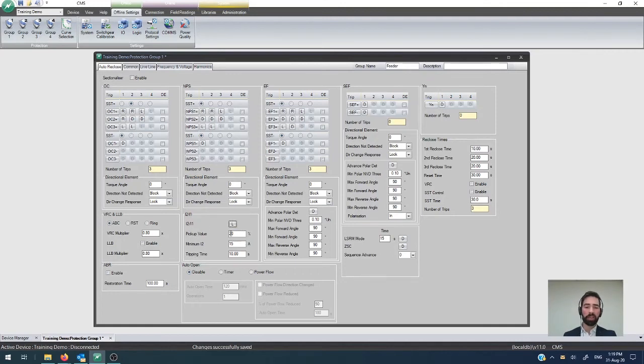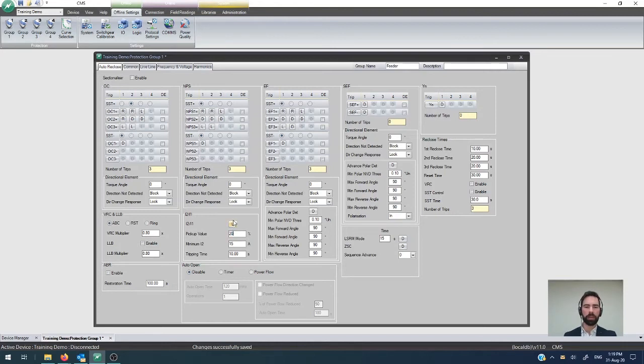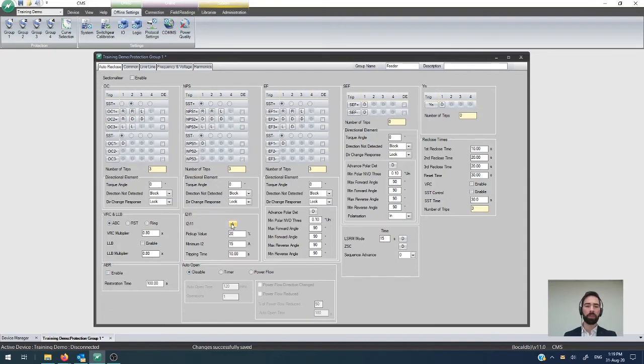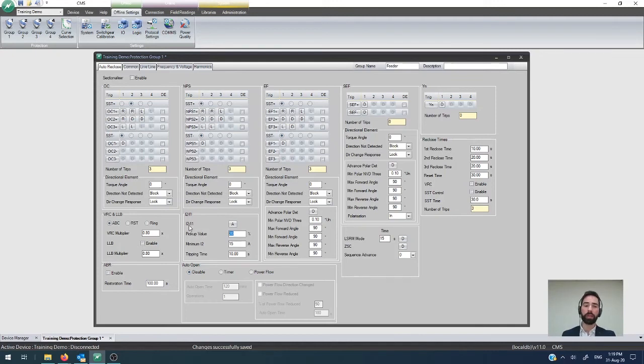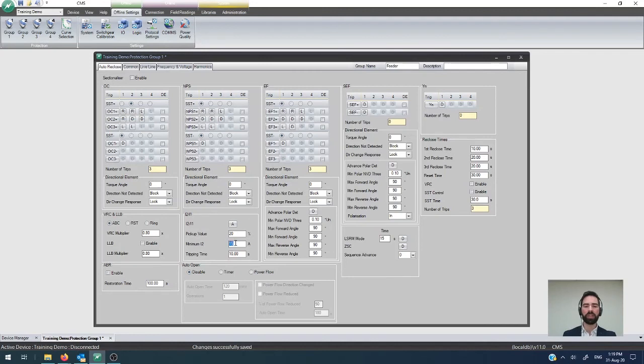The pickup value here is a percentage, 20% by default, which covers most of the cases. I will say it's worth having a look at with an alarm to ensure you don't get spurious tripping, to sort of get a feel for where your level needs to be on your network in a practical sense. Then we also have the minimum i2. One of the limitations with i2 on i1 is that if you have very low currents, it doesn't take an awful lot to get to that 20% threshold. But once you cross say 15 amps of i2, that implies that you can have a substantial load there, so you mitigate the risk of spurious trip and you can configure your tripping time down below.